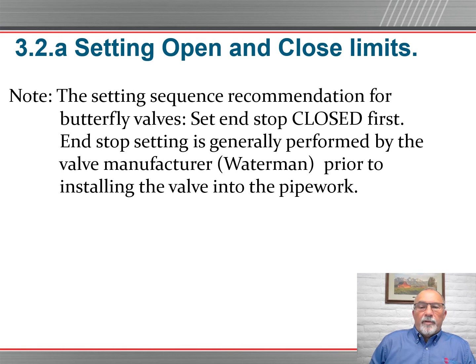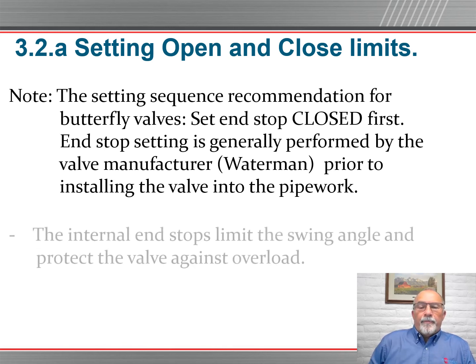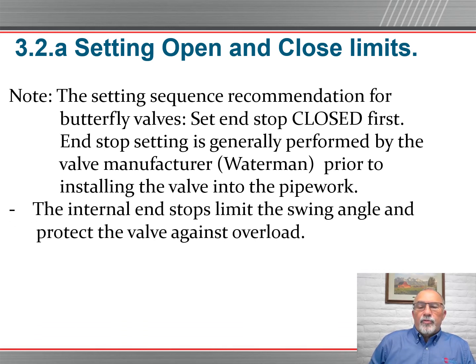The setting sequence recommendation for butterfly valves: set end stop closed first. So always think about the closed position first. That's where you set. The end stop setting is generally performed by the valve manufacturer. Waterman sets this prior to shipping. The internal end stops limit swing angle and protect the valve against overload. Sometimes the contractor has to adjust the mount of the gearbox, and then these closed positions on the gearbox have to be reset. In general, only one end stop closed must be set, since the swing angle of the valve is already set for 90 degrees in the factory.